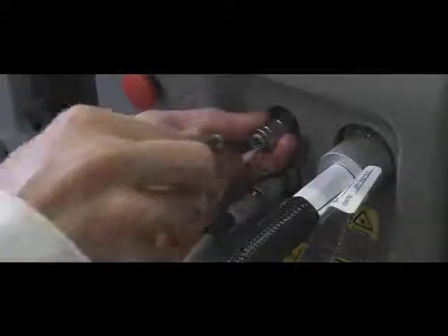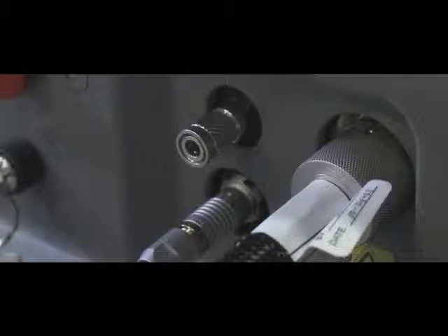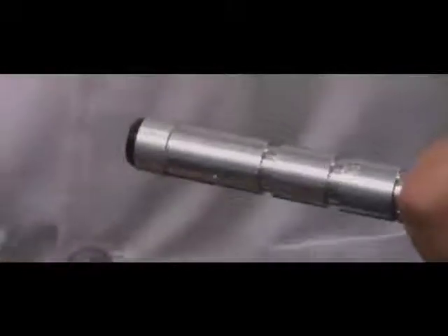When attaching the cryogen line, you must push in the metal attachment and insert the line. The metal attachment will spring back, securing the line. To release, once again push in the metal attachment. The valve is under pressure and you will hear a rushing sound. The handpiece components are the filter, button release for slider attachment, inner tube for slider, and window holder.